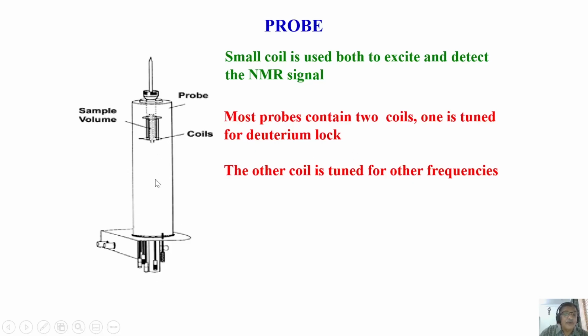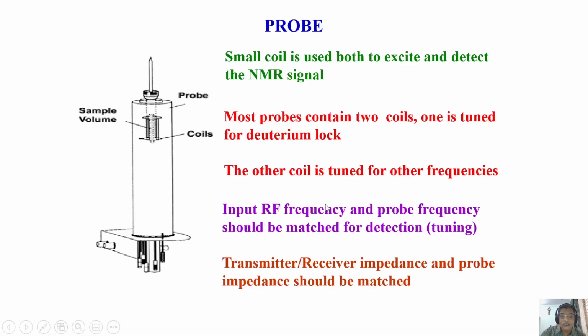That's why different probes are designed for different spectrometers. You cannot take a probe for 300 megahertz and start putting it into an 800 megahertz spectrometer and record the spectrum. It is not possible, because the coil is tuned for a particular frequency. This is for the deuterium lock, deuterium frequency. Okay, you can tune it. And then beyond a certain thing, of course, there is a problem. You cannot have this for all the frequencies. One coil is for the deuterium lock, the other is tuned for other frequencies, and the deuterium lock is used for preventing the field drift. This is called a field frequency lock, for which we use this.